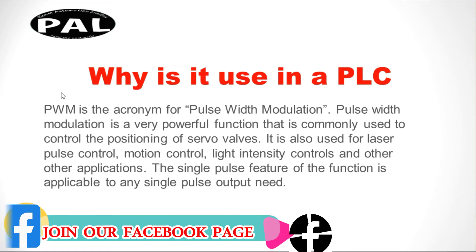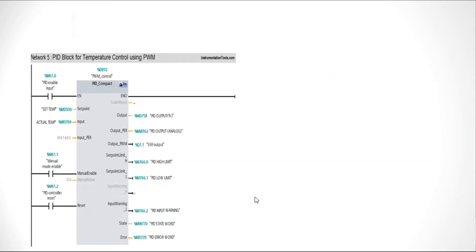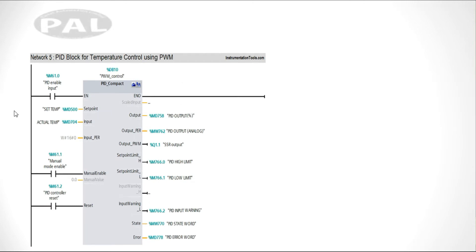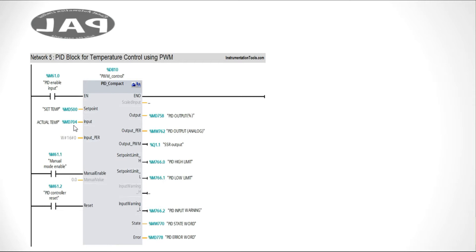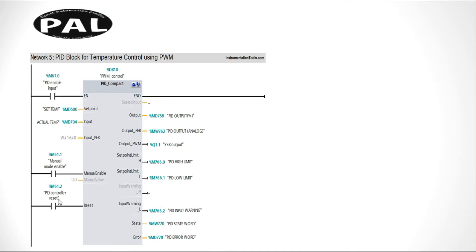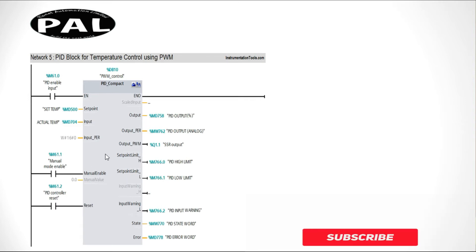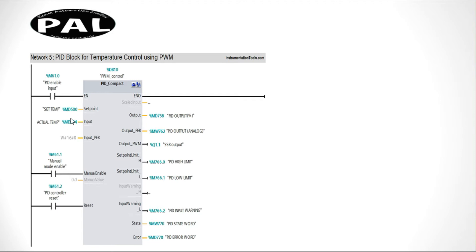PWM is very useful across many industry sectors. For example, in PLC-based temperature control, there is a 1200 PLC programming frequency, PID enable input, set temperature, memory data register, and actual temperature. The set temperature and actual temperature are compared, which controls your output via PID control and reset. Pulse width modulation connects to PID compact. The output PWM is controlled by an analog input signal, such as from an RTD or thermocouple.